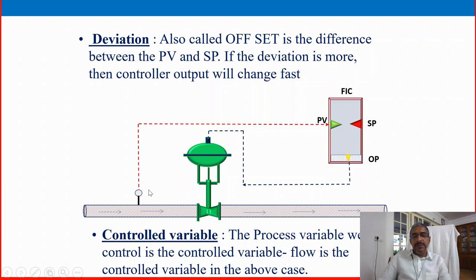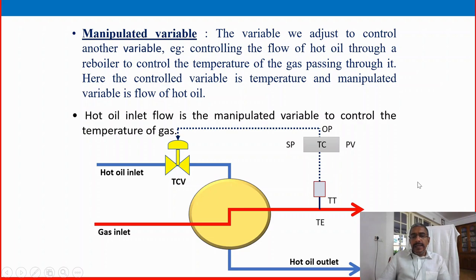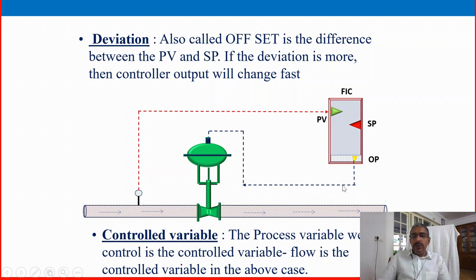We have studied: primary element and transmitter — transmitter producing an output of PV (process variable); the controller FIC; SP the set point; output — the produced signal; and the controlled variable and final control. A manipulated variable is the variable we adjust to control another variable. Example: controlling the flow of hot oil through a reboiler to control the temperature of the gas passing through it — here the controlled variable is temperature and the manipulated variable is the flow of hot oil.